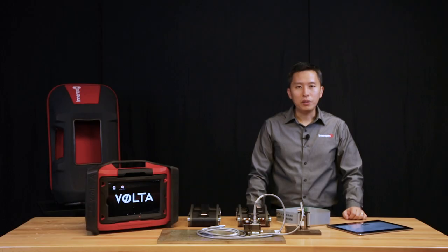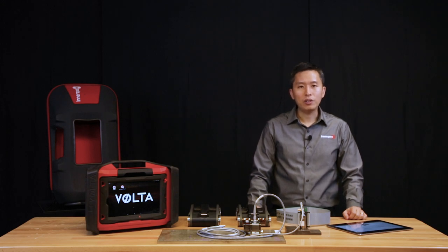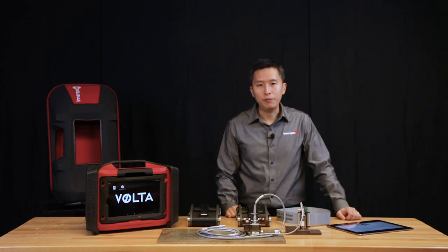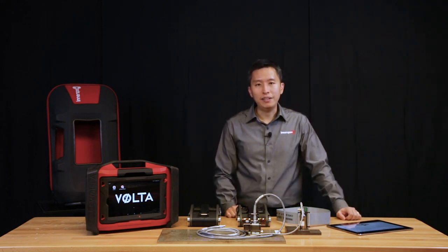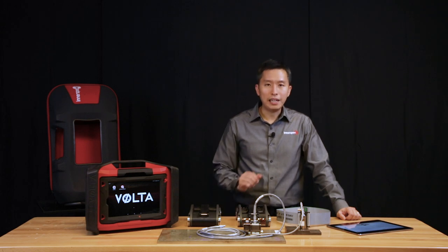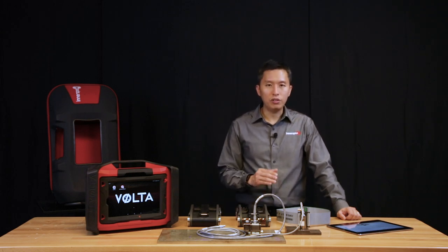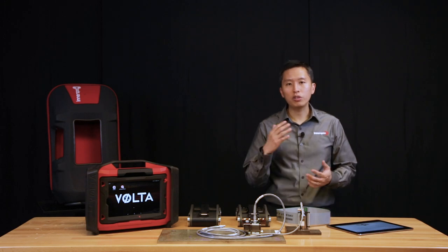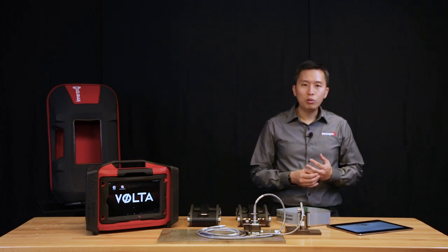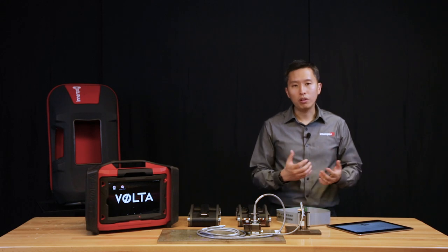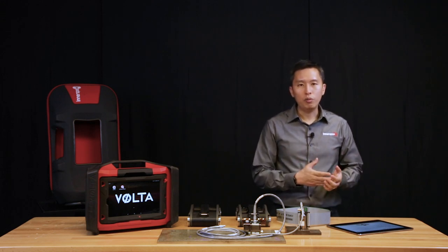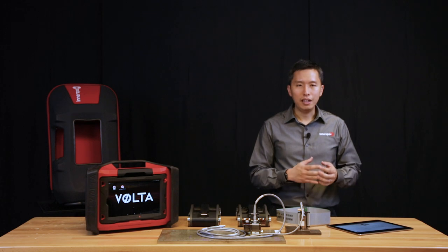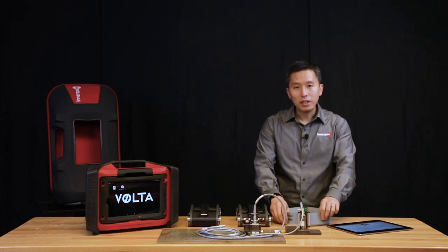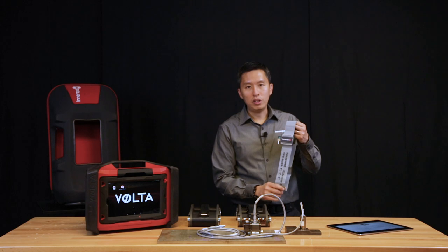For this next segment, I will discuss the long-range UT technique, or the LRUT technique. For Innerspec Technology, our LRUT technique is based on a joint development with our partner FBS Incorporated, and it is a patented technology. It uses the magnetostrictive technique, so it uses the magnetostrictive force to generate torsional wave mode. There are two modes of inspection, one of which is currently under development and another which we have released. The one that we have released is known as the axisymmetry inspection.